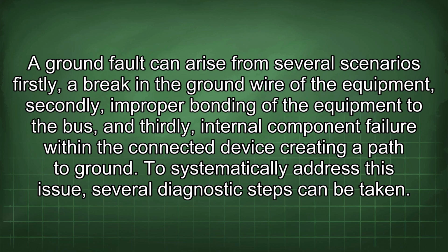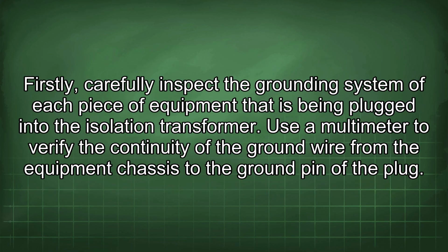Firstly, a break in the ground wire of the equipment. Secondly, improper bonding of the equipment to the bus. And thirdly, internal component failure within the connected device, creating a path to ground. To systematically address this issue, several diagnostic steps can be taken. Firstly, carefully inspect the grounding system of each piece of equipment that is being plugged into the isolation transformer.